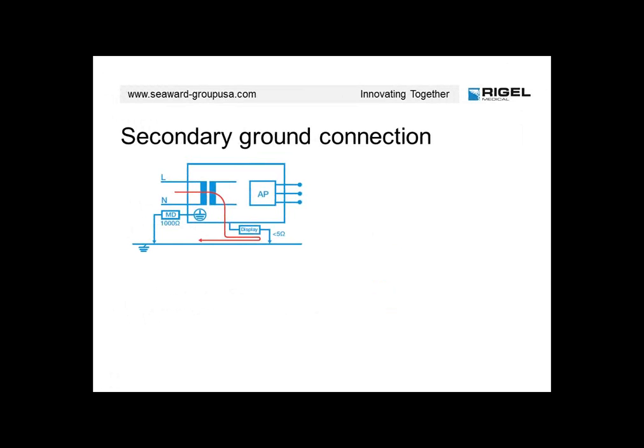Another feature of both the 288 and the 62353 is it will identify if there's a secondary ground connection. Pretty common if you have a piece of equipment that is connected to other equipment, where if you have a display connected to a D connector, there could be an alternative ground path there that could be less resistance than the 1000 ohm body model used to identify the leakage current itself. So in this particular case, there is such a connection, and you see the current path, which will take the path of least resistance, going to ground and bypassing the body model and the measuring device.